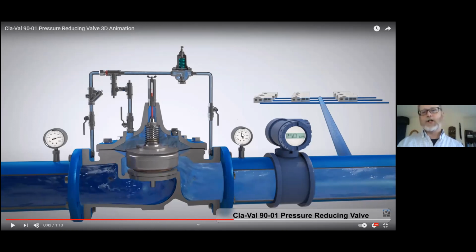And you can see the pressure, even though the flow is dropping now, the pressure is starting to build up because the higher pressure is moving and there's no demand in our neighborhood. So as the demand stops, the pressure comes up, and that's getting to a threshold where now the valve is told, again, just based on how it's plumbed, to start to close.